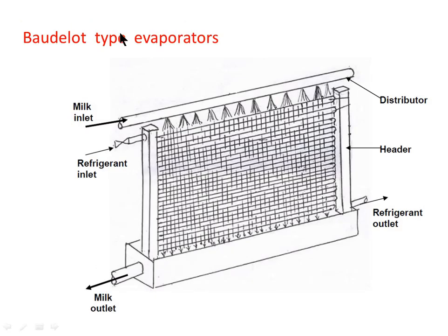Next are the Baudelot type evaporators. These consist of a series of horizontal pipes, one under another, connected to form a circuit. They can be either dry or flooded. Refrigerant flows through the tubes while chilled liquid flows in a thin film over the outside in counter-flow direction, collected in a trough at the bottom. These evaporators were generally used for cooling milk, wine, and water, since it is possible to chill to very nearly the freeze point without damaging the equipment.